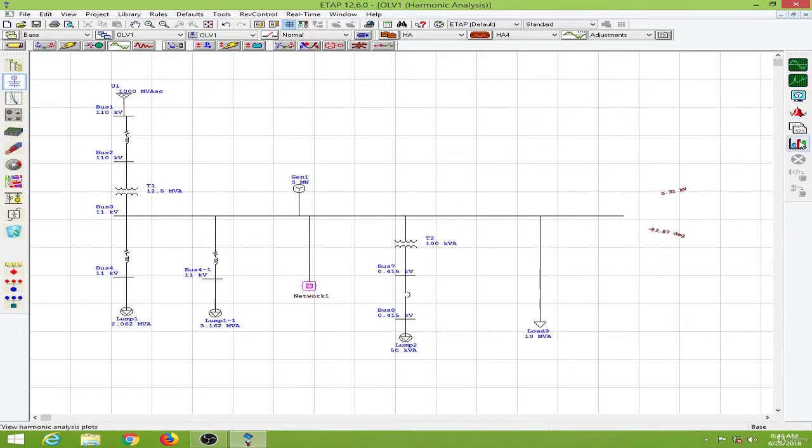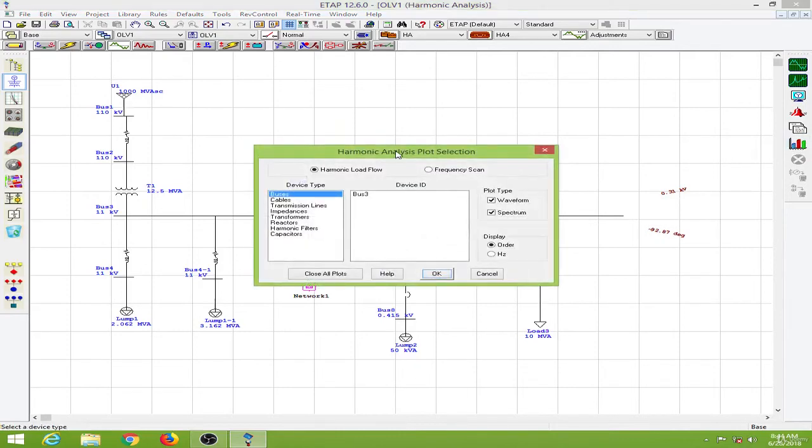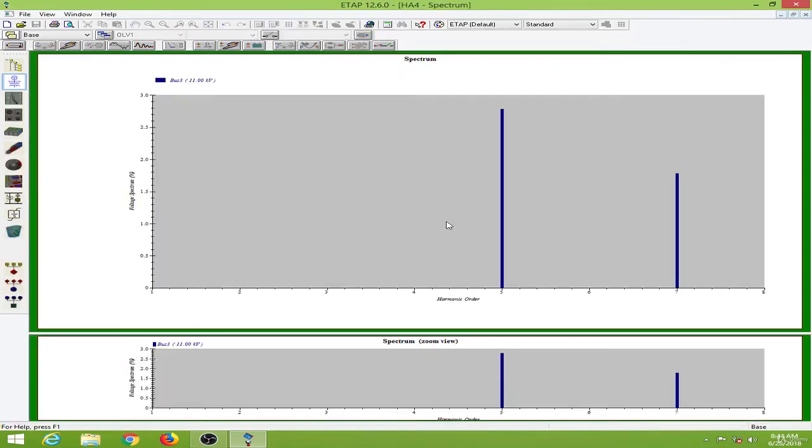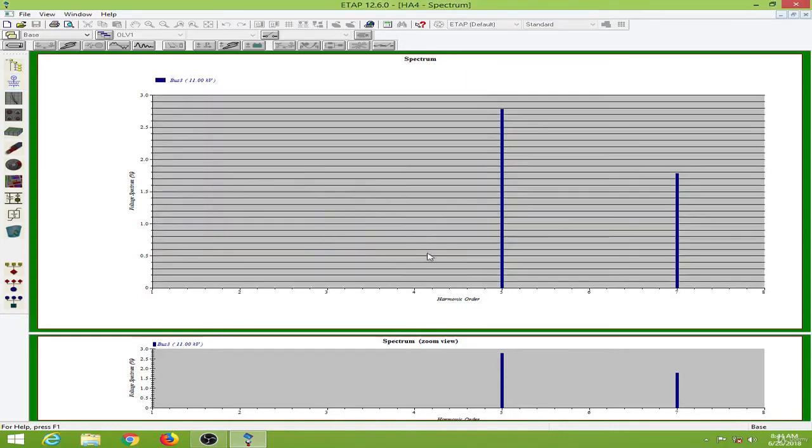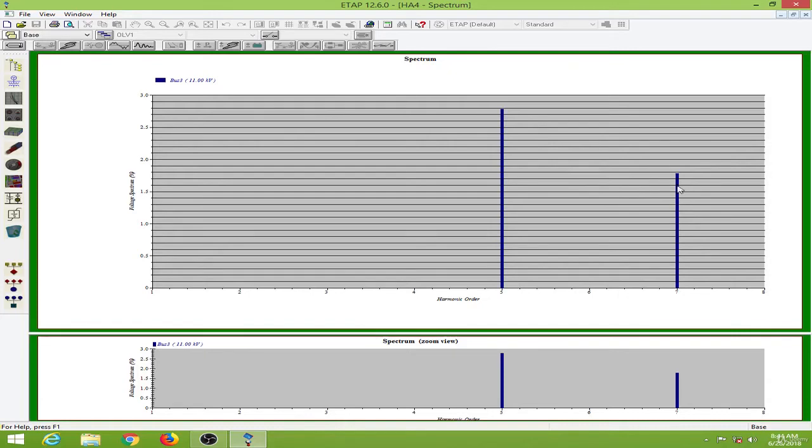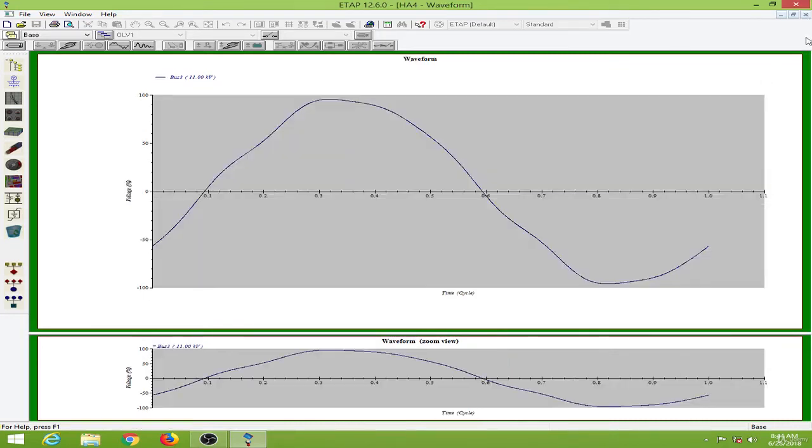Now let's go to plot over here. Then I will select the waveform and the spectrum for the bus 3. So as you can see the fifth order harmonic magnitude is about 2.8. And here this is about 1.8. Seventh harmonic is about 1.8. So this is the distorted waveform over here.